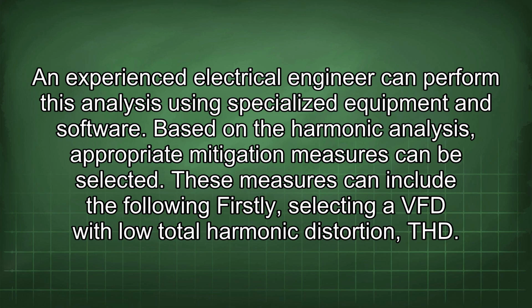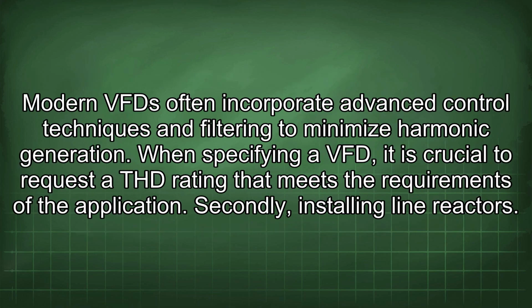Firstly, selecting a VFD with low total harmonic distortion, THD. Modern VFDs often incorporate advanced control techniques and filtering to minimize harmonic generation. When specifying a VFD, it is crucial to request a THD rating that meets the requirements of the application.